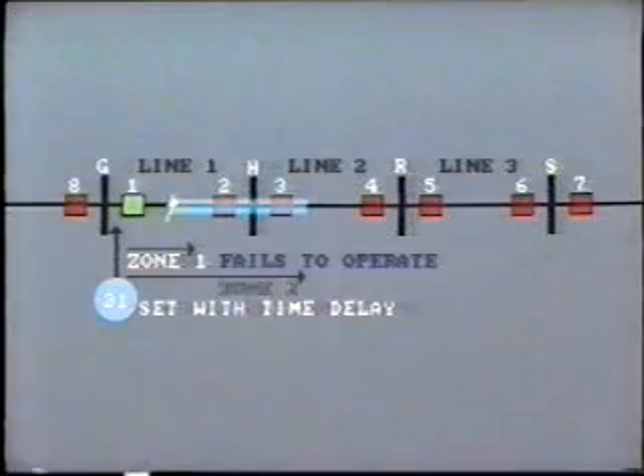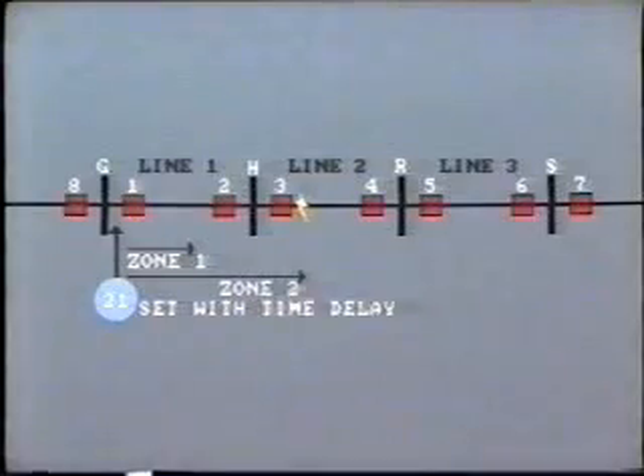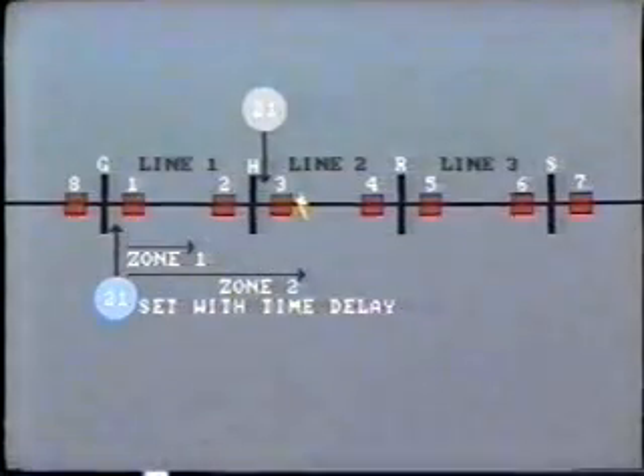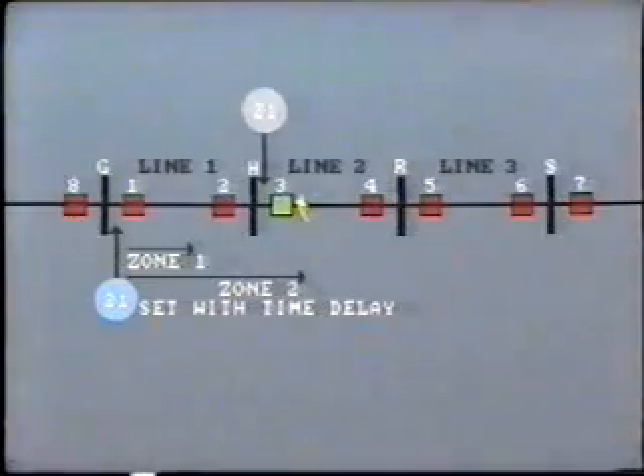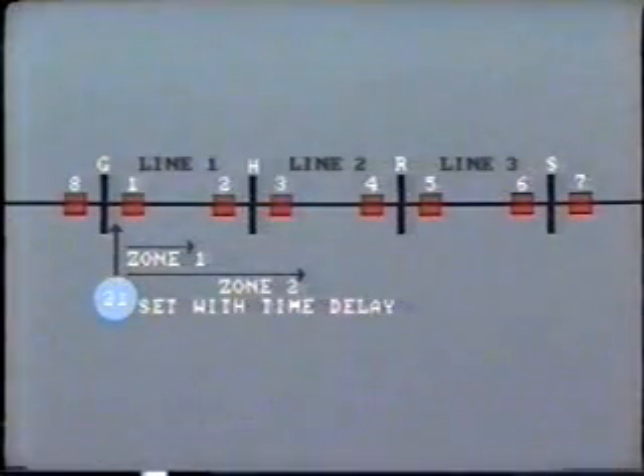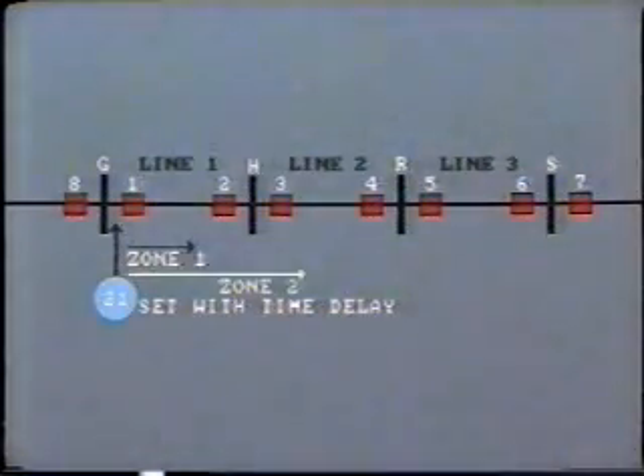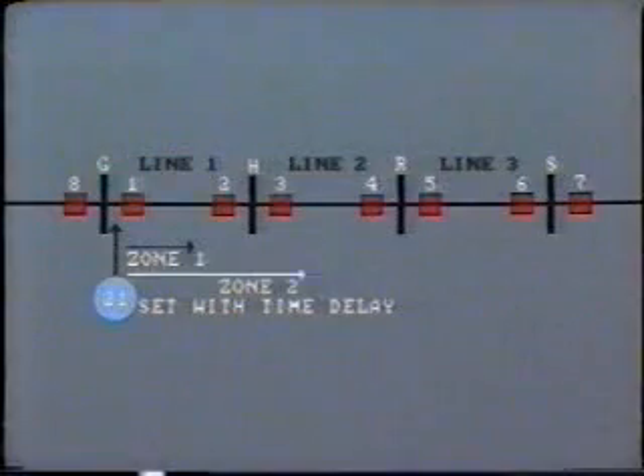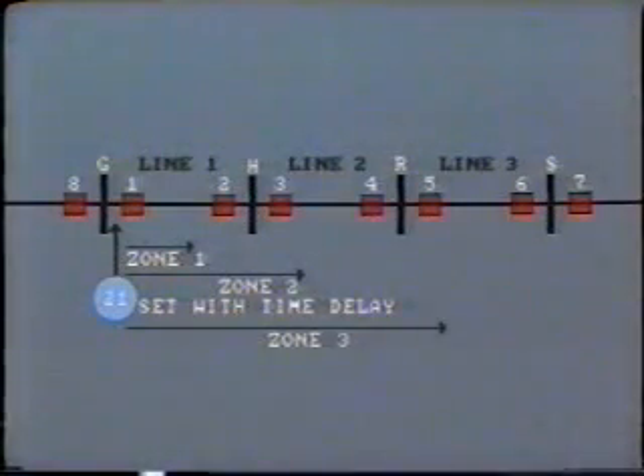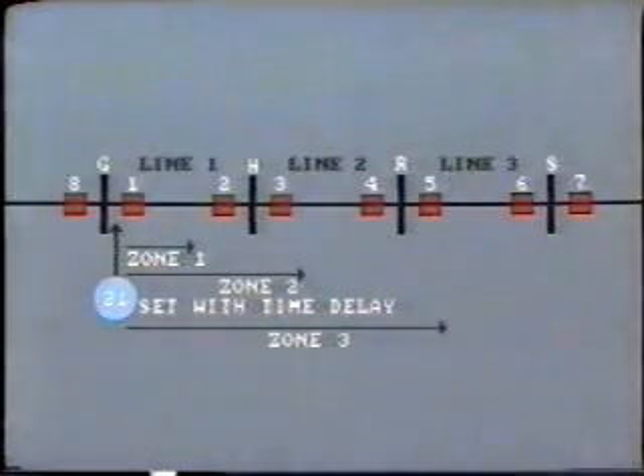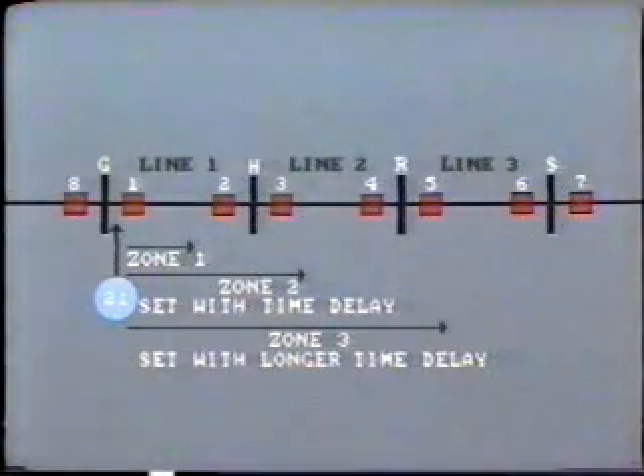It will also operate for a fault for the remaining 20% of line 1, and it will operate for a fault in the first part of line number 2. However, the time delay should allow the local protection at bus H to operate first in order to protect line 2. The coordination diagram here shows Zone 2 stretching from bus G and into line 2. Similarly, the relay is equipped with a third zone of protection, which stretches into line 3. This is set with yet a longer time delay.